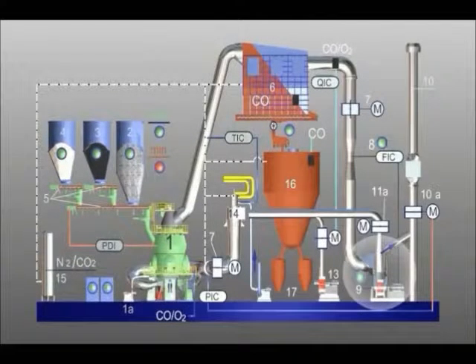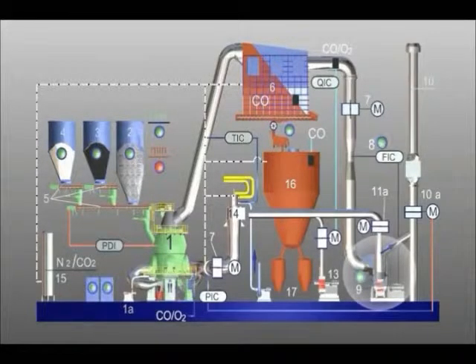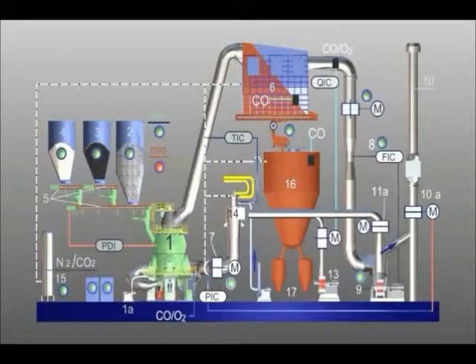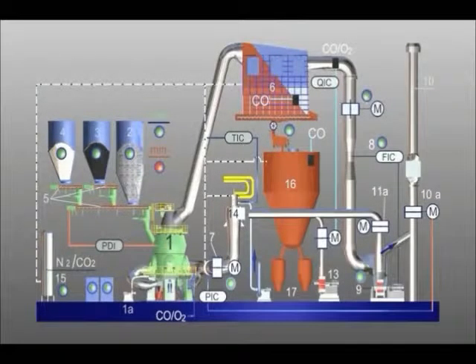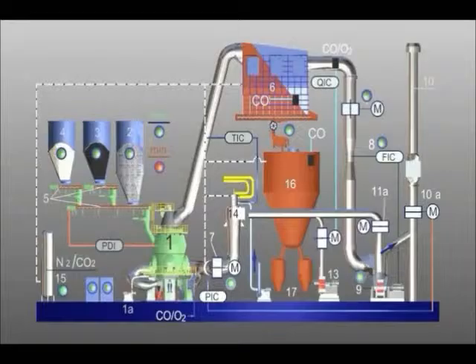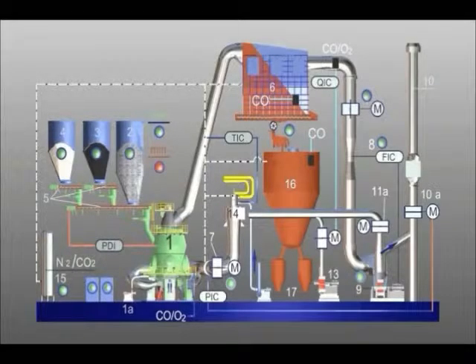The flap valves upstream of the mill and downstream of the filter at position seven are opened. The process gas fan at position nine is started up and operated with a minimum volume flow. The plant is inertized by feeding in nitrogen or carbon dioxide from the corresponding dispensing vessel at position 15.